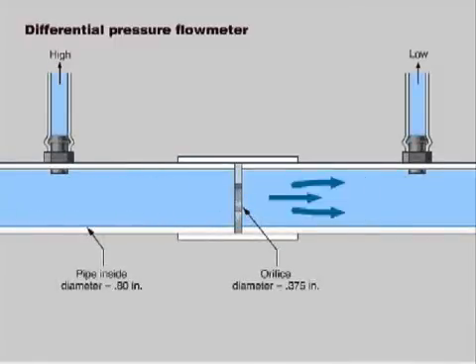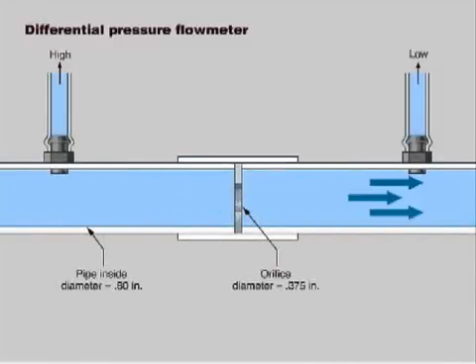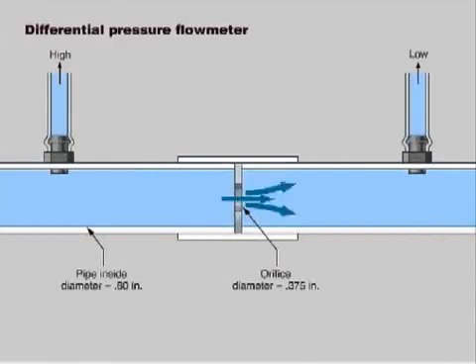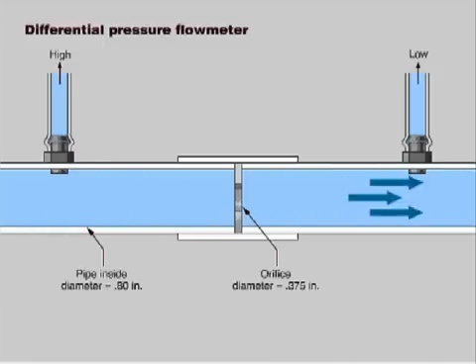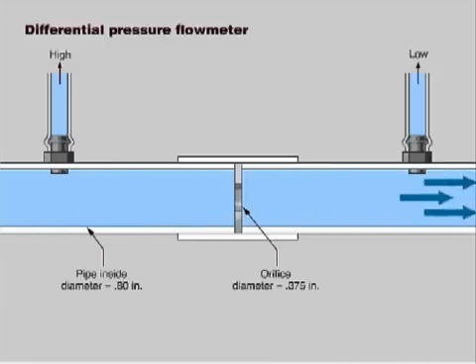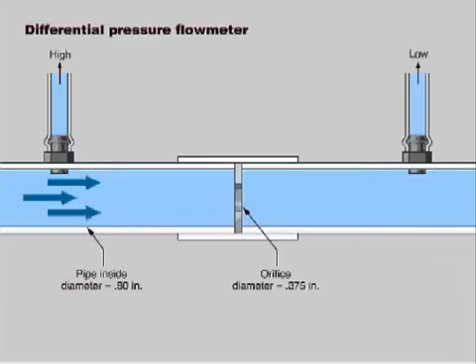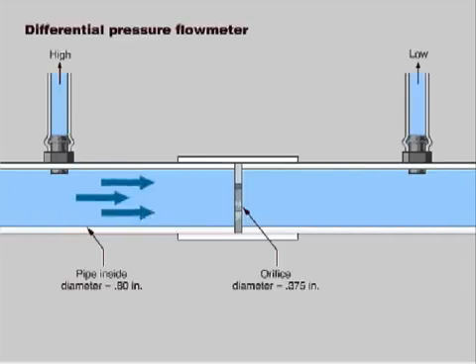The concept is very simple. If you place a restriction in the flow, there will be a pressure loss that is proportional to the flow rate. The more fluid you try to jam through the restriction, the greater the pressure loss. So if you measure the differential pressure, you can use it to calculate the flow rate.